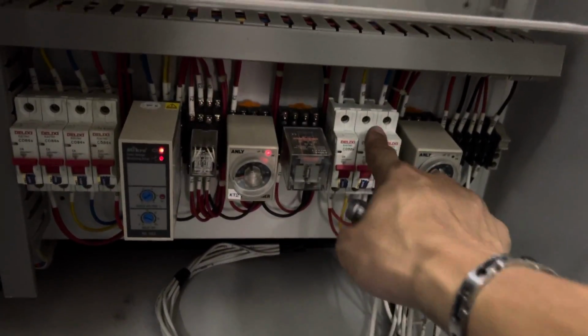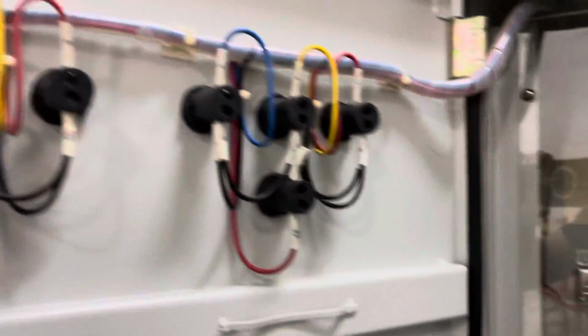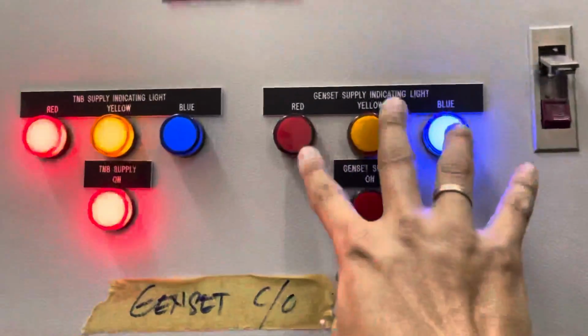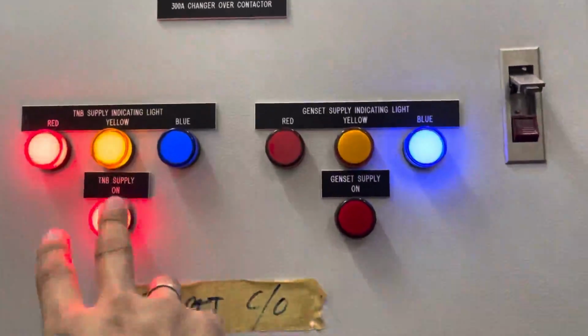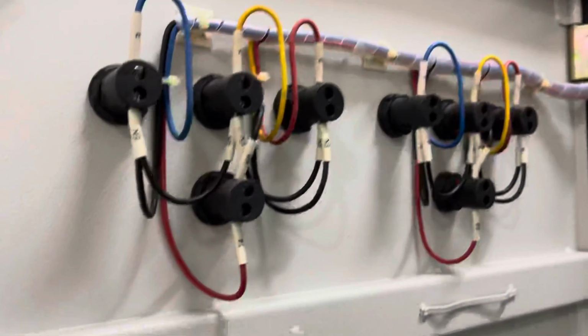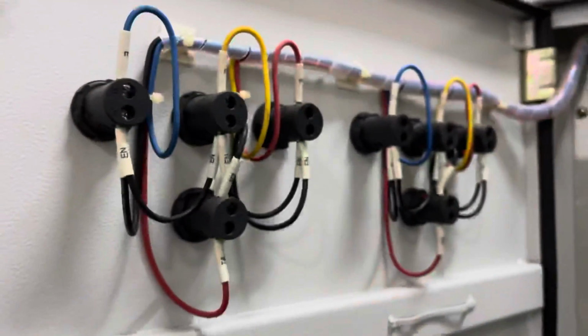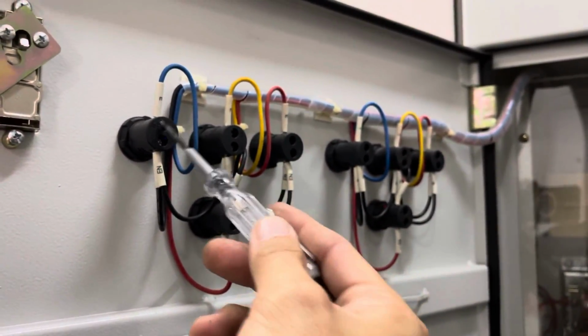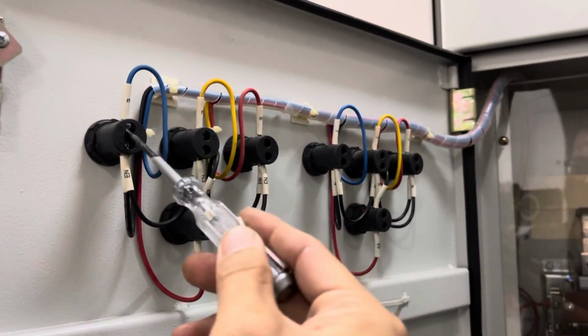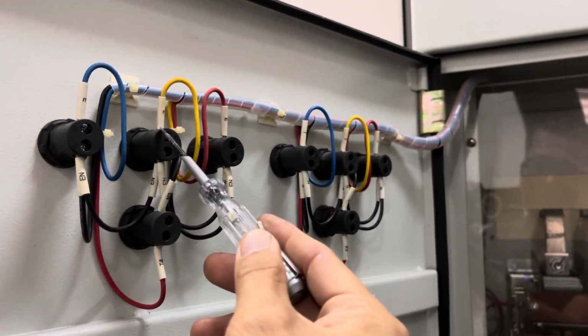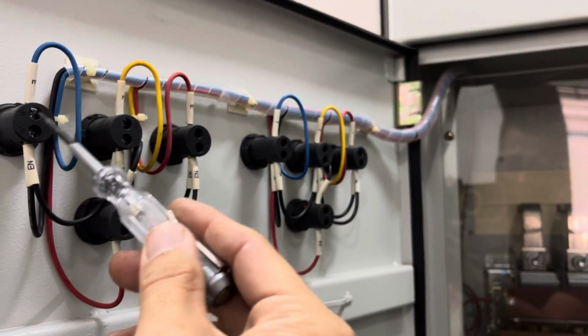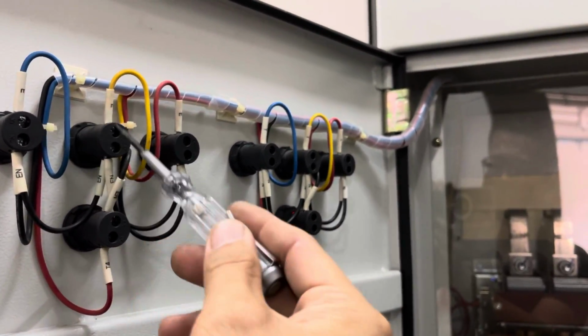Okay, after you on here, there will be power supply available here. Okay, but there's no change over. So from here, if you have a multimeter, you can check the frequency here. And then you can check single phase voltage and check the 415 voltage. If you check the voltage 415 and 240 is okay, that means the AVR is okay.